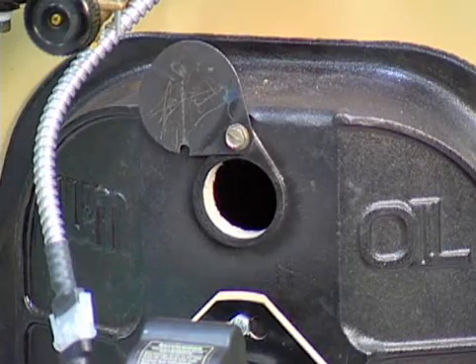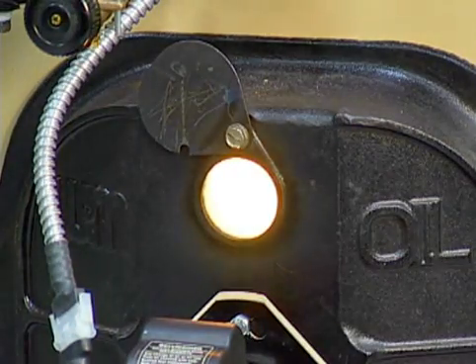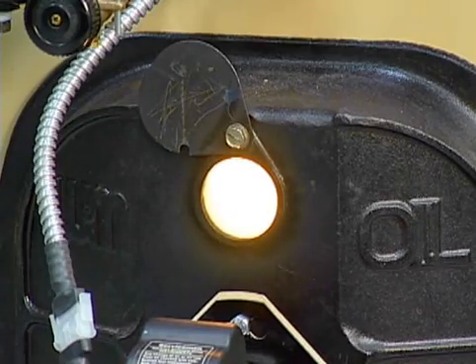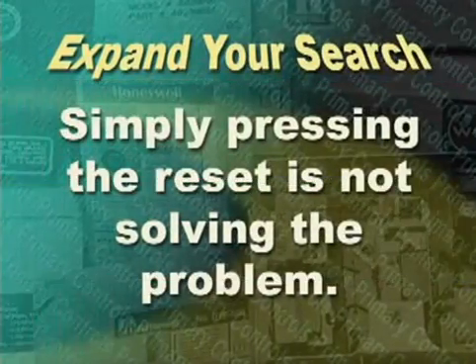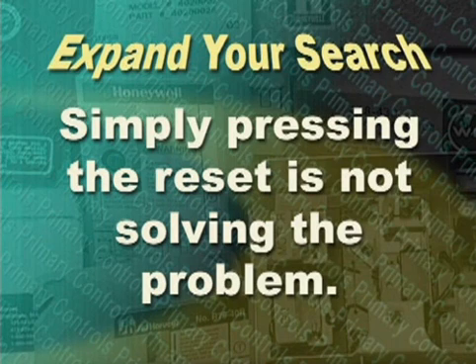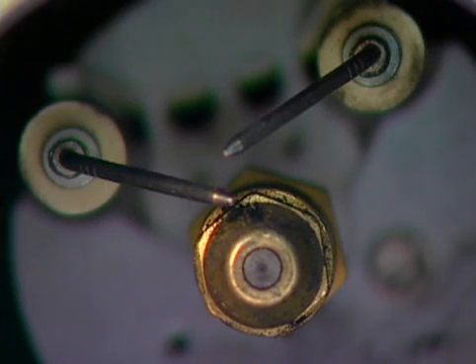If the burner starts and continues to run normally after you push the reset button, your job still isn't over. Simply pressing the reset button is not solving the problem. You must find the reason why the unit went off on safety and take action to keep it from happening again.